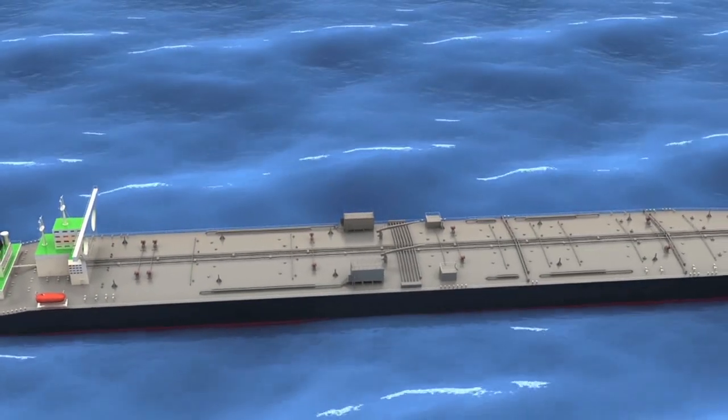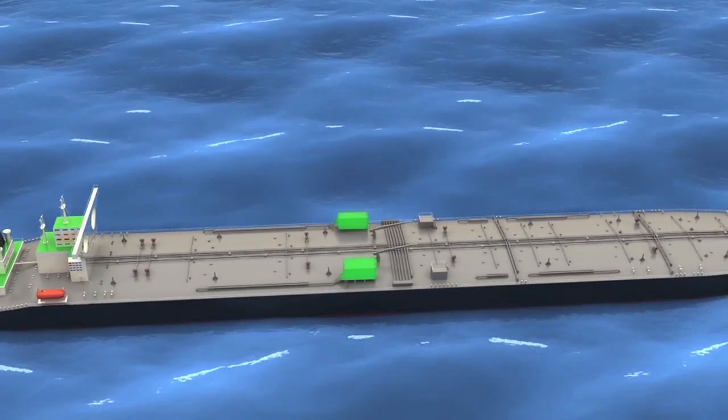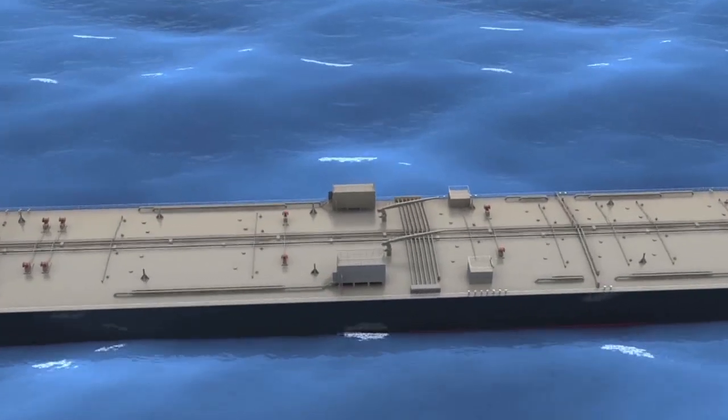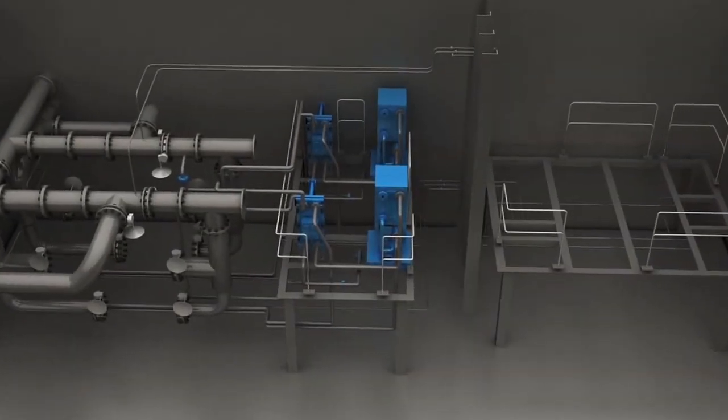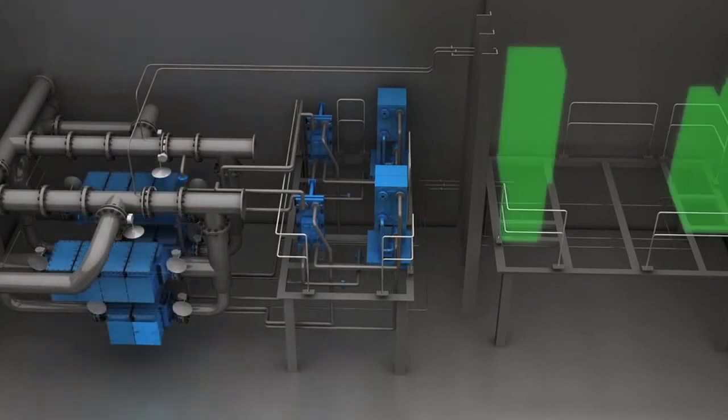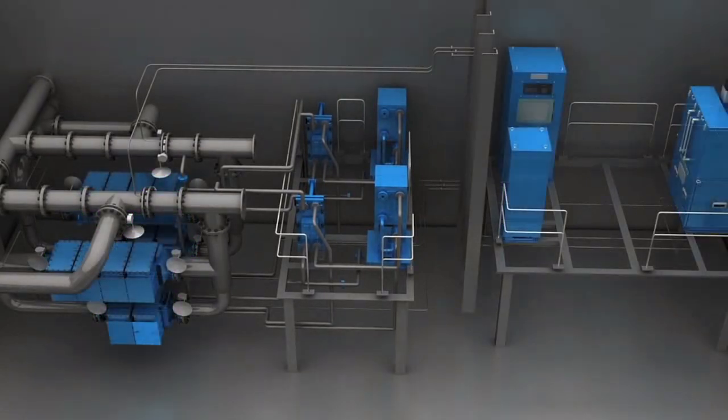If there is no pump room but submerged ballast pump, you can make a safety room on deck. Explosion-proof type ECU and other equipment are installed in this room with skid mount type. The other non-explosive equipment is in the engine room for aft peak tanks.